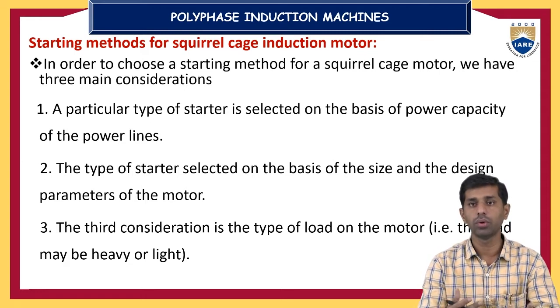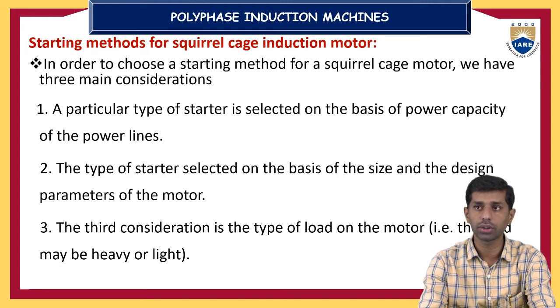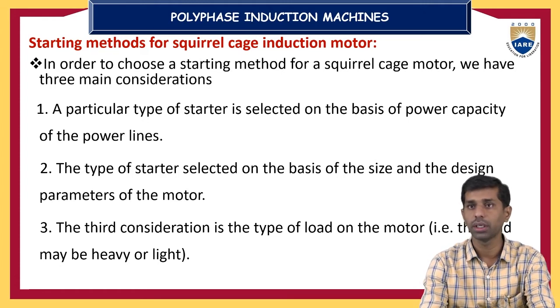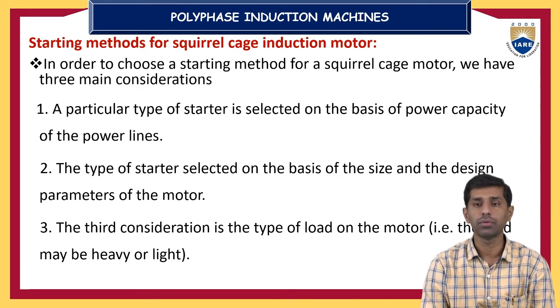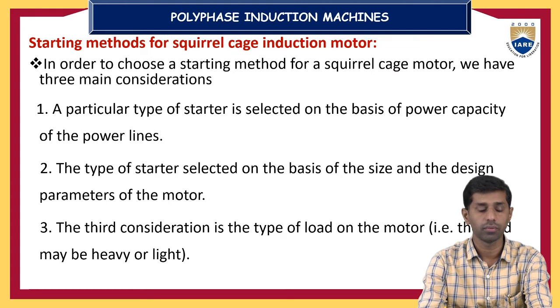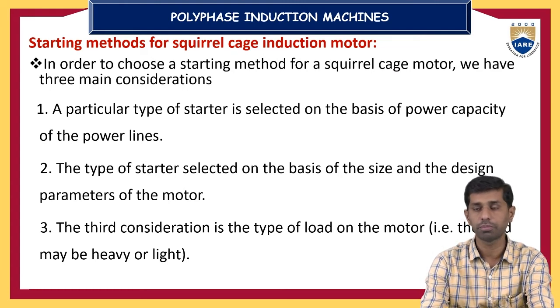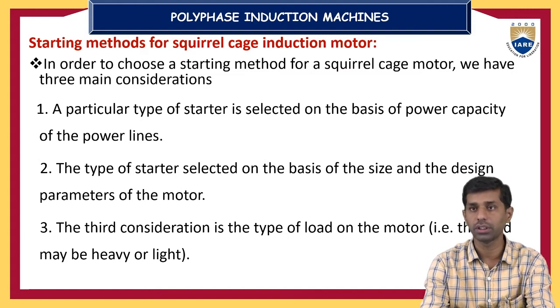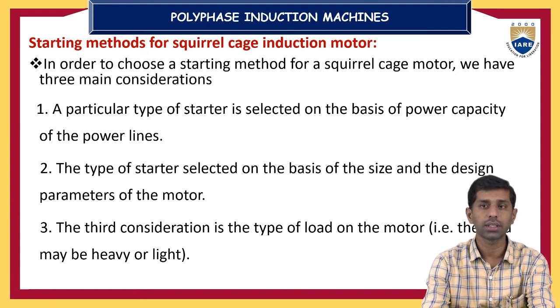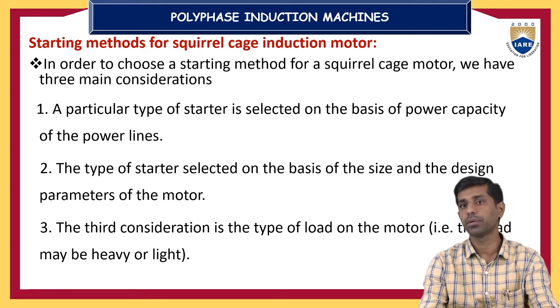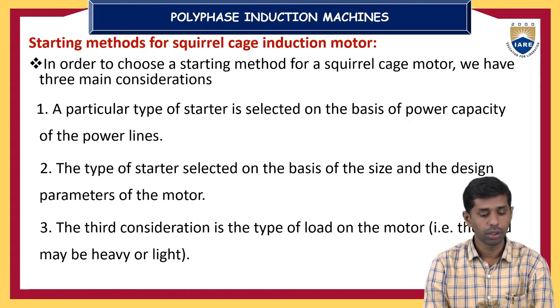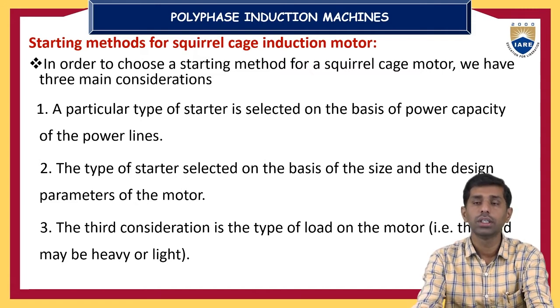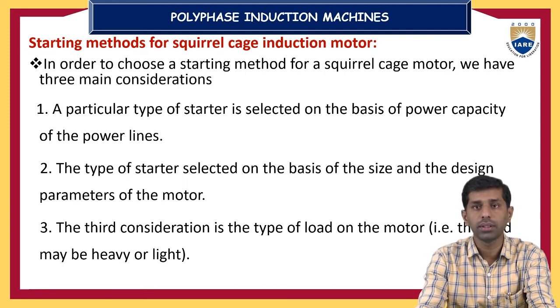When we talk about the starting methods for a squirrel cage induction motor, we have three main considerations when choosing a starting method for a particular type of machine. Number one, a particular type of starter is selected on the basis of the power capacity of the power lines. Based on the power capacity, we have to consider which kind of starter is suitable for the induction motor. The second point, the type of starter is selected on the basis of the size and the design parameters of the motor. The third consideration is the type of load on the motor, that is, whether the load is heavy or light.